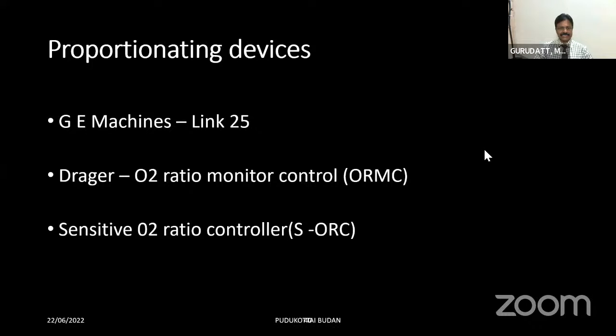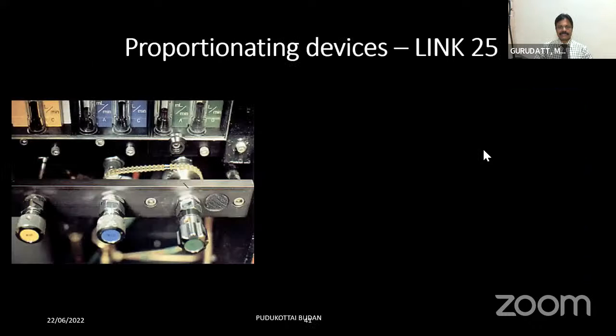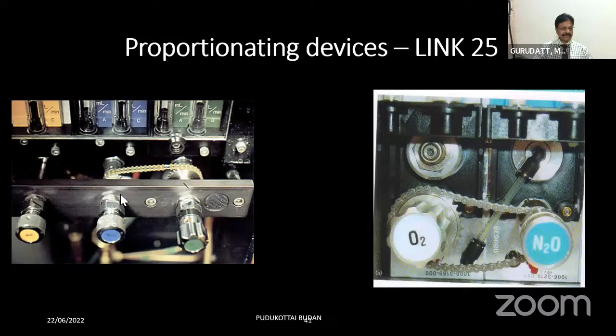Let me discuss this Link 25 first. The Link 25 is present distal to the flow control knobs and before the flow control valves. You have separate sprockets for oxygen and for nitrous oxide. The oxygen sprockets are 29 in number and the nitrous oxide sprockets are about 15 in number. That means if you rotate the nitrous oxide flow control knob 2 times, the oxygen flow control knob will rotate once. That means a ratio of 2:1 between nitrous oxide and oxygen will be maintained.